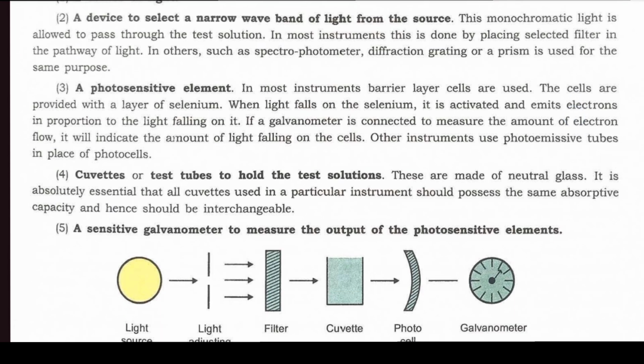Fourth, cuvette or test tube to hold the test solutions. These are made of neutral glass. It is absolutely essential that all cuvettes used in a particular instrument should possess the same absorptive capacity and hence should be interchangeable.